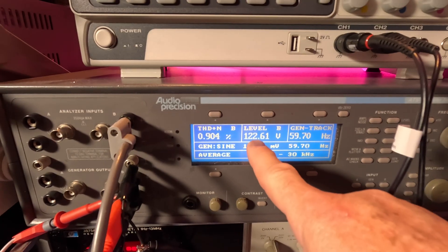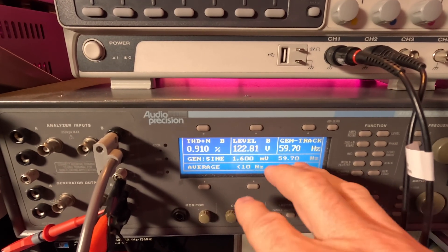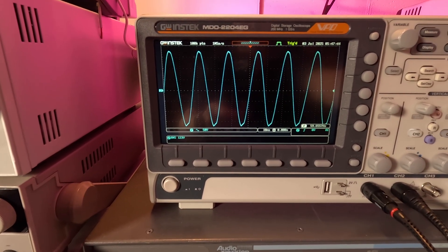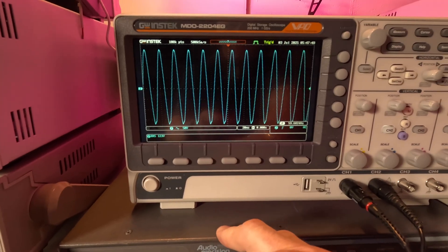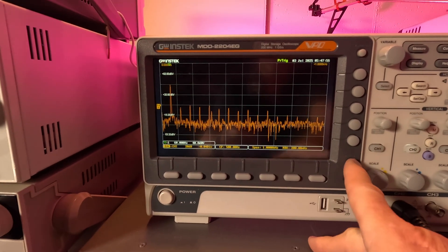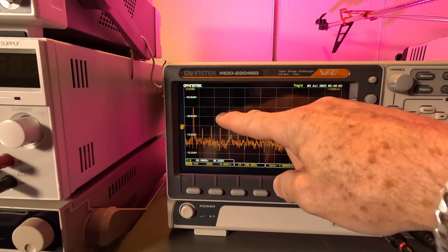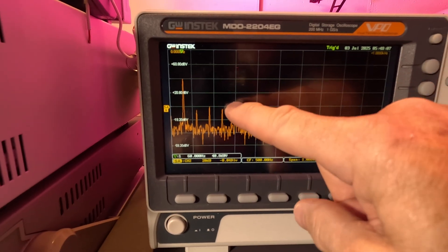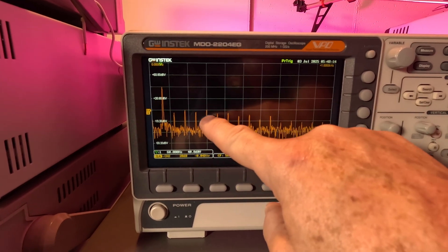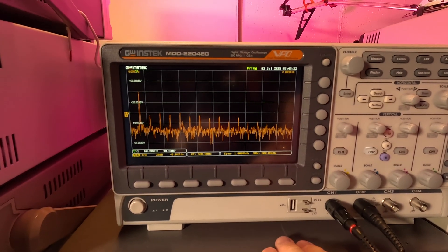It shows 122 volts down here and 123 up here — it's bouncing around because the upper reading is taking a more constant reading. Looking at the spectrum: here's the 60 Hz fundamental and here are the harmonics, 20 dB per division — so 20, 40 dB down. The next highest peaks are about 40 dB below the fundamental. Even on the odd harmonics there's not a big difference between them — it's just kind of wavy. That's what it looks like at no load.